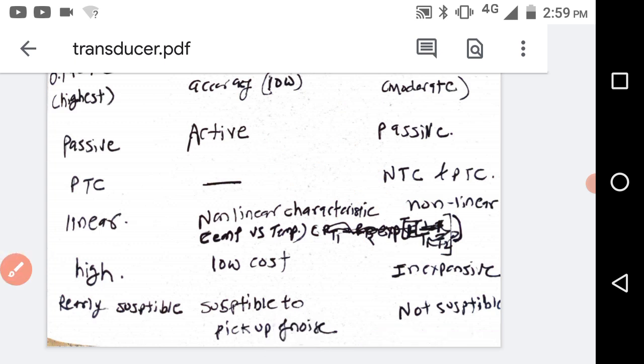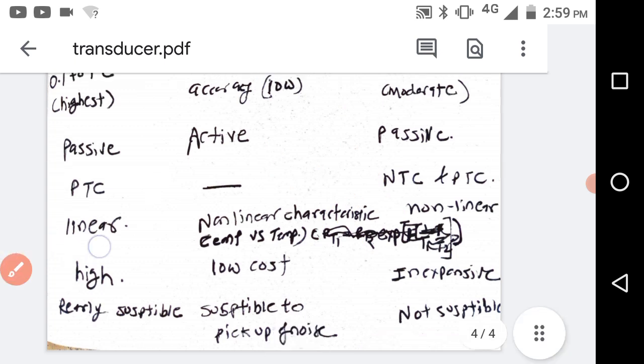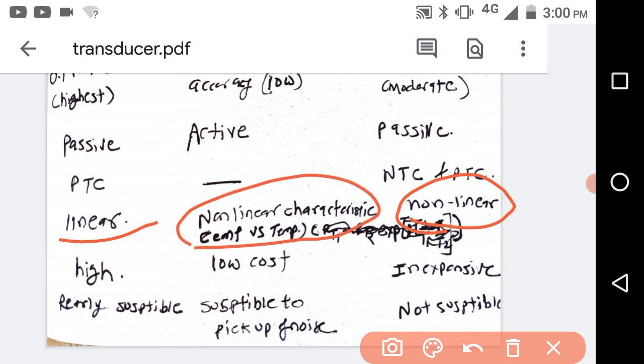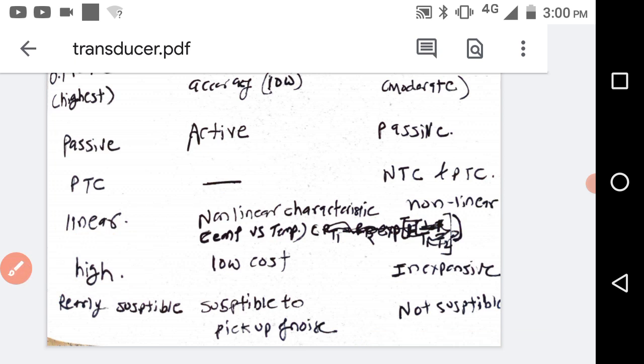So what is the characteristic between the temperature and the resistance change? It is linear in case of RTD, and in case of the thermistor it is non-linear. And EMF versus temperature in case of the thermocouple is also non-linear. So highest cost is of RTD. Then a thermocouple is susceptible to the noise and the RTD and thermistors are not susceptible to the noise. These are the differences between the three temperature sensors.